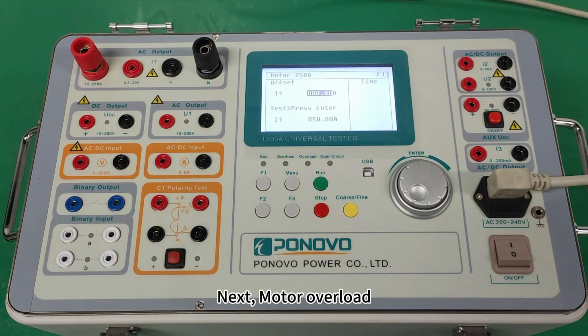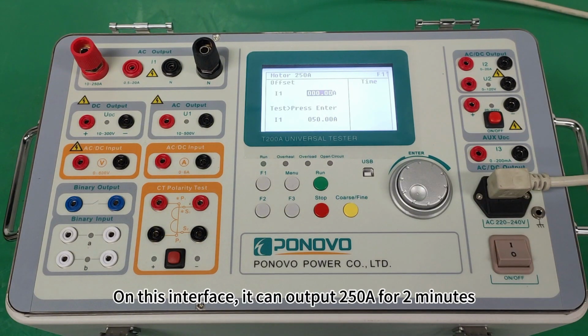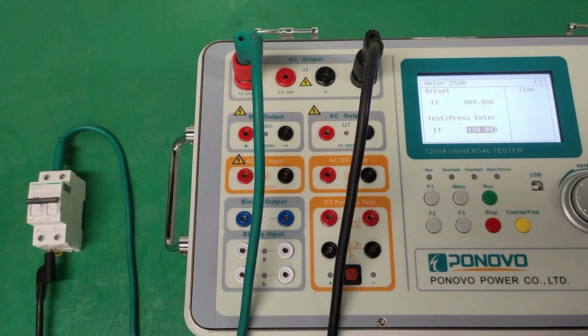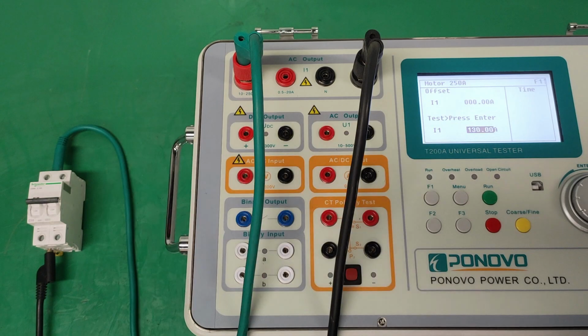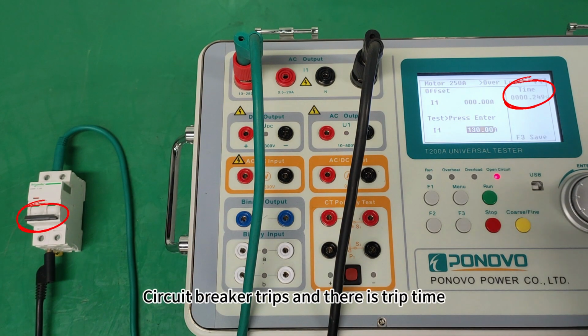Next, motor overload. On this interface, it can output 250 amperes for 2 minutes. Now we test a C16 circuit breaker as an example. Press Run button. Circuit breaker trips and there is trip time.